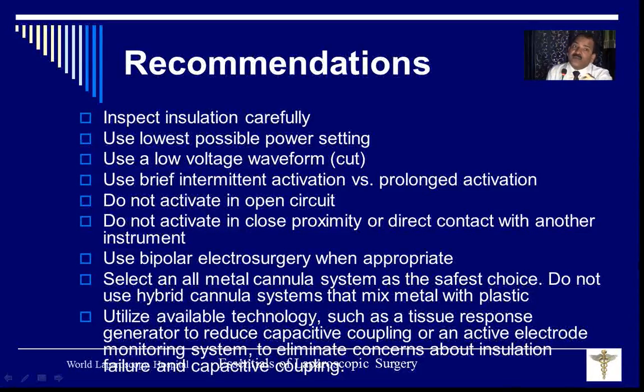Use bipolar whenever appropriate. Whenever it is possible, always bipolar. Monopolar should only be used where bipolar cannot work, like cutting, like fulguration. But wherever you have to desiccate, use bipolar. Select an all-metal cannula system as the safest choice. Do not use a hybrid cannula system that mixes metal with plastic, to prevent capacitive coupling. Utilize available technology such as tissue response generator to reduce capacitive coupling, or active electrode monitoring system to eliminate the concern about insulation failure and capacitive coupling.